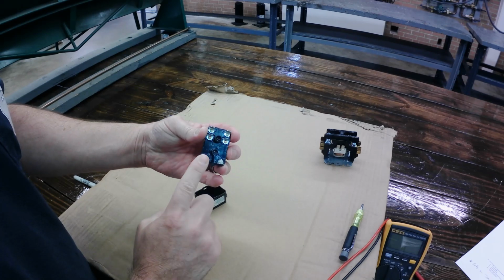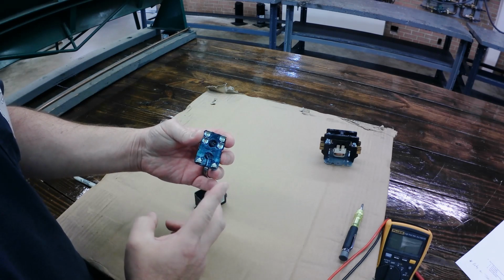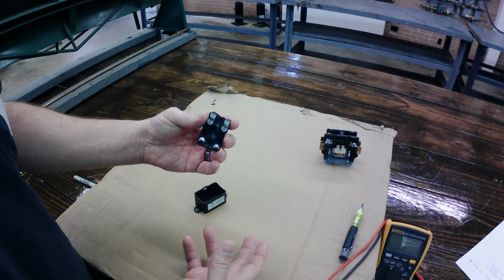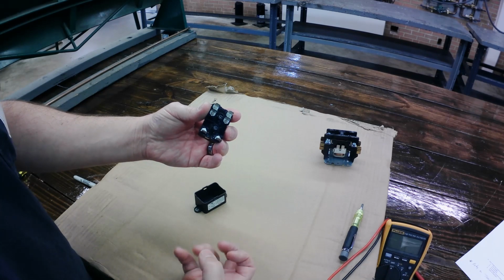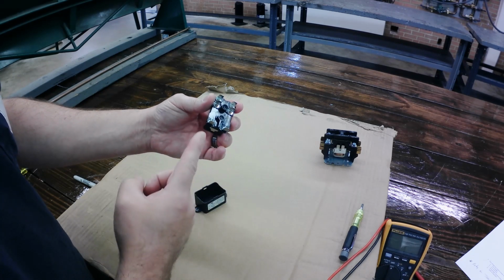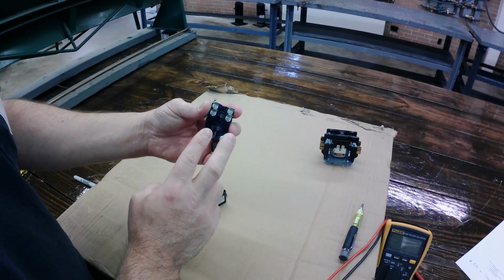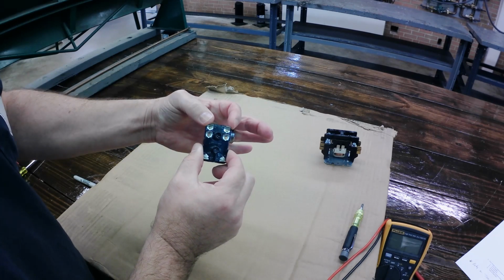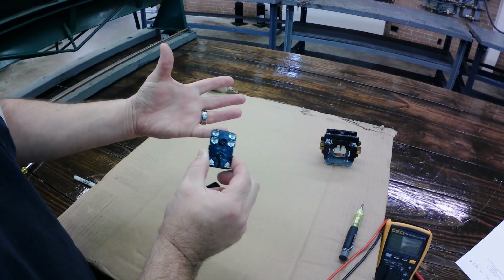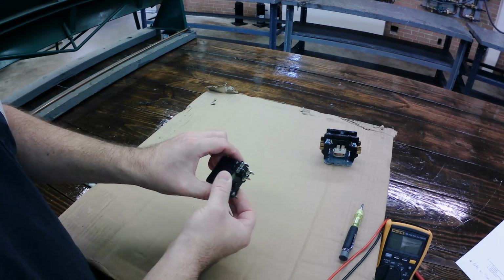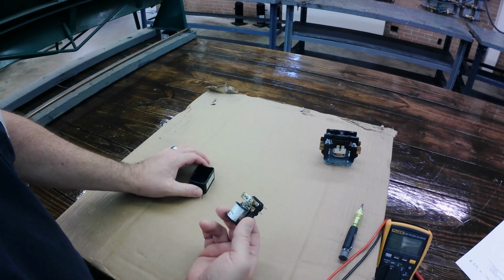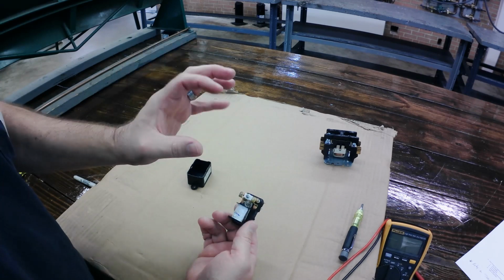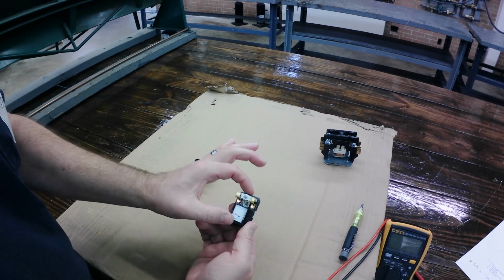Coil at the bottom. This coil is going to be energized by the thermostat, and it's going to be tied into the G circuit, the indoor fan relay circuit. So once this coil gets power down here on terminals 1 and 3, then 2 and 4 will close and 5 and 6 will open. Too easy. What I think people are confusing themselves on is they're not remembering that there's two parts to this.